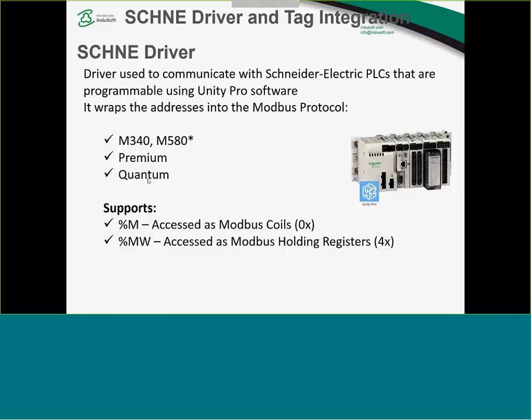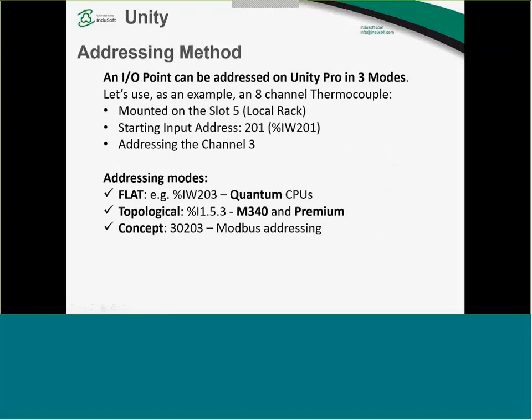This driver, the SCHNE driver, supports two addresses only, which are the %M, the binary addresses, and the %MW, the word or analog addresses with formats in different options like floating, double words, and words, as you're going to see pretty soon. So that's the driver that's going to run behind the tag integration to Schneider.